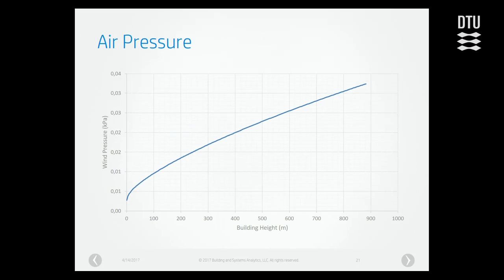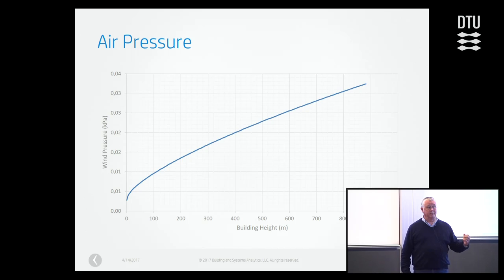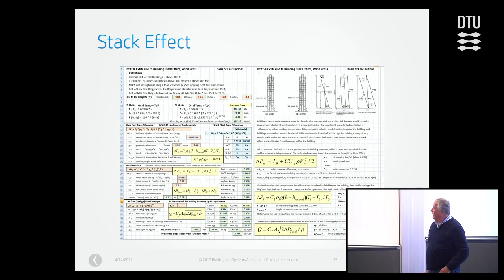So then the other one is air pressure. This is a really great one when you think of physics - when you start looking at the speed of a fan, you don't look at air as cubic meters per second, but as kilograms per second, because as we go up, the pressure of the air changes, and also the density of the air changes. So it's like doing work in Mexico City or something - the fans are going to start spinning because there's no weight of the air to go around. You're not going to get any air at the end of the ductwork.